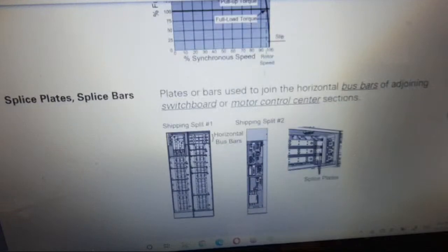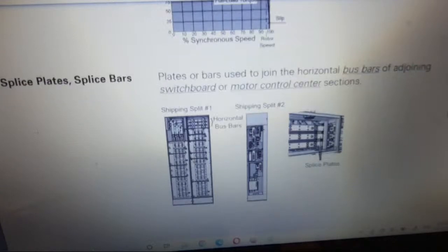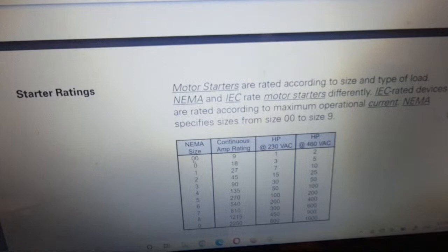Splice plates, splice bars, plates or bars used to join the horizontal bars of adjoining switchboard or motor control center sections. Starter rating, motor starters are rated according to the size and type of the load. NEMA and IEC rate motor starters differently. IEC rated devices are rated according to the maximum operational current. NEMA specifies sizes from 00 to size 9.